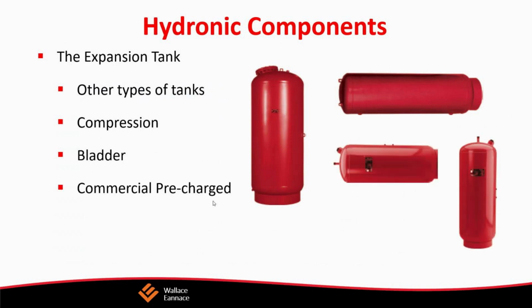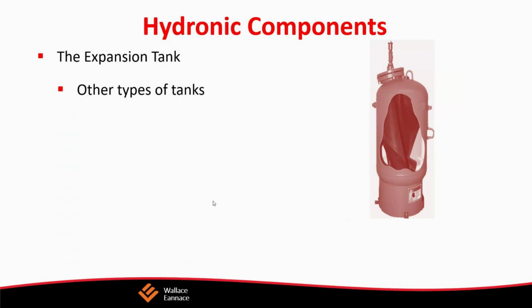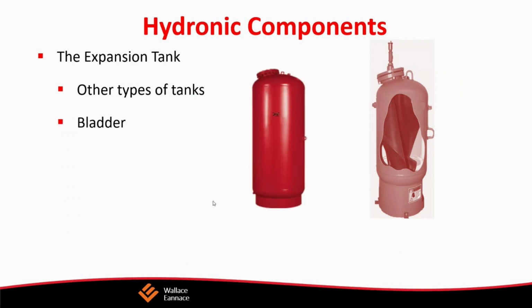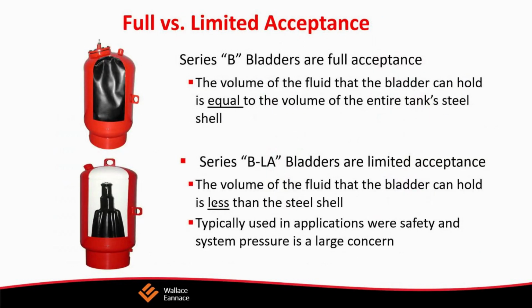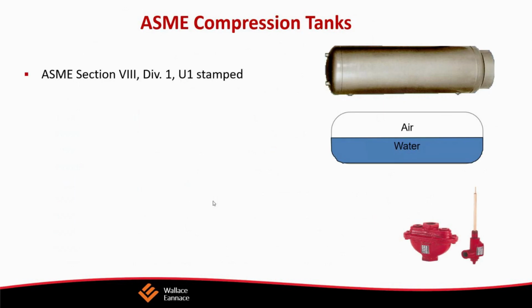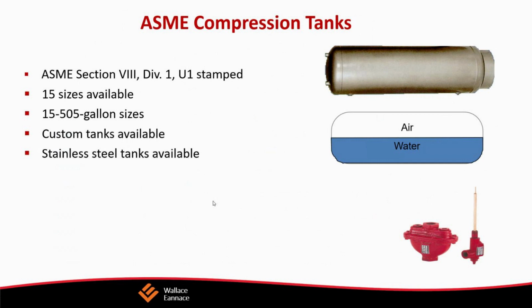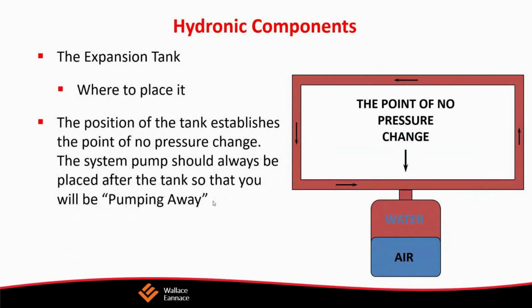It provides a spring, and it maintains a minimum pressure set inside the system. Keep in mind, water does not compress. So that added volume is going to have to go somewhere, and that's what the expansion tank is for. This is the tank before installation. We set the system's initial operating pressure, and then there is the maximum pressure and temperature of the fluid. So you can see that as the system initially starts, it expands a little bit, and when it's at maximum temperature, it'll expand more. The air and the water pressures must match before the system is filled. So you need to set the pressure level of the expansion tank before you connect it to the system.